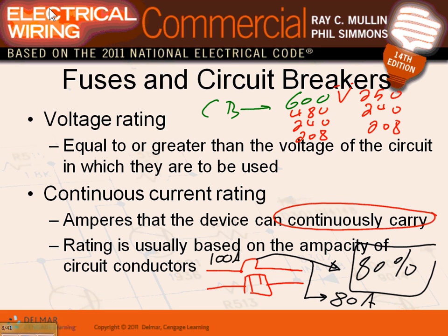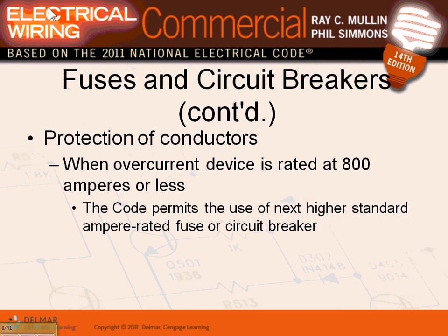Next quarter, when we get into a commercial building, 4,000 amp, industrial building, 4,000 amp, we're going to talk about something called 100% rated circuit breakers. If the circuit breaker says 4,000, we're going to pull 4,000 continuously forever because it's stamped with a UL rating for 100% rated. Otherwise, all these circuit breakers that you're looking at, and fuses, are rated for 80% of their continuous rating. Do you guys remember that rule?